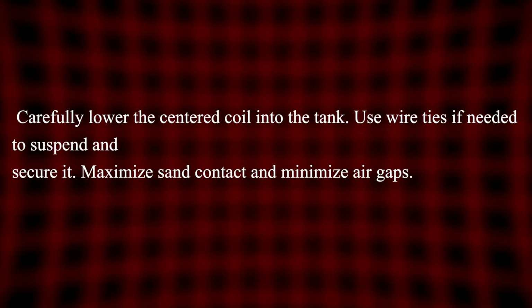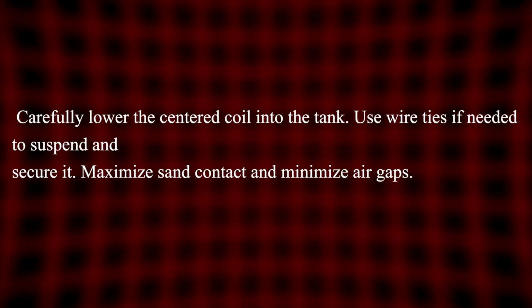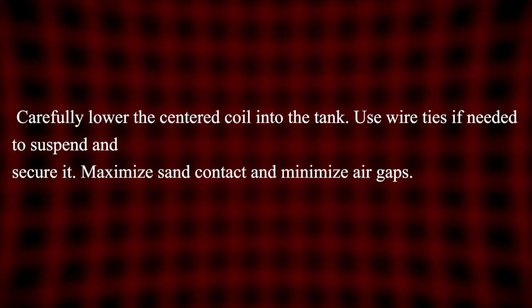Step 5. Carefully lower the centered coil into the tank. Use wire ties if needed to suspend and secure it. Maximize sand contact and minimize air gaps. Filling the tank follows 2 unbreakable rules. First, the sand must be completely dry.